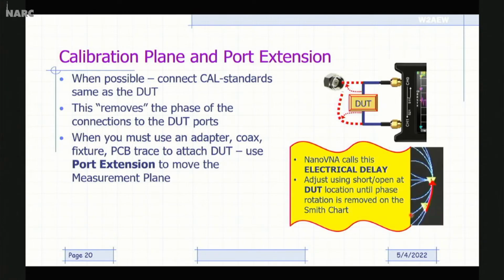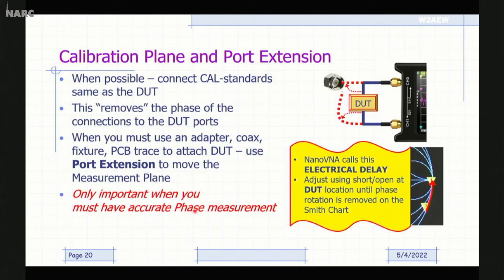And then you can actually use the Smith chart. Again, a little beyond what we're going to go into in this talk, but you can use the Smith chart to adjust the electrical delay until you indicate a perfect open or a perfect short, and therefore account for that extra delay and move the reference plane to your actual device. Again, only important when you're generally operating at very high frequencies and where you need an accurate phase measurement at the DUT. Like if you're going to design a matching network to solder down to the circuit board at a PCB antenna, for example. Okay.